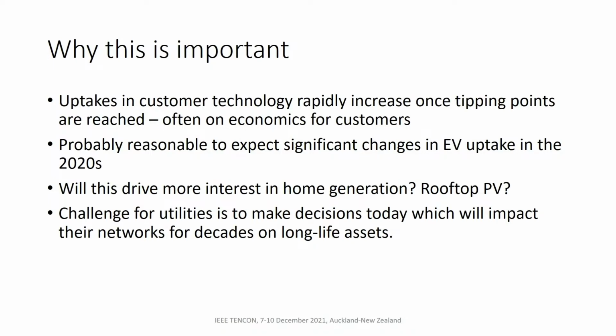expected of a transformer. We're also looking at the fact that we have other things which are DC based, things like EV charging, that's going that way. So we can start to see more power electronics coming on the system. We're also seeing more rooftop PV and home generation. One of the big problems the utilities have is how to make decisions today. If they're looking at choosing or upgrading or replacing something right now, and they're expecting to have it for 50 years, and they really do try and look out over the next 50-year period, the simplest decisions might just be the MVA or kVA size, or whether they're looking at different voltage levels, those sorts of ideas. But if we now throw into the mix a possibility in the future that we may just get rid of the AC and have DC, then it provides them something else to think about.